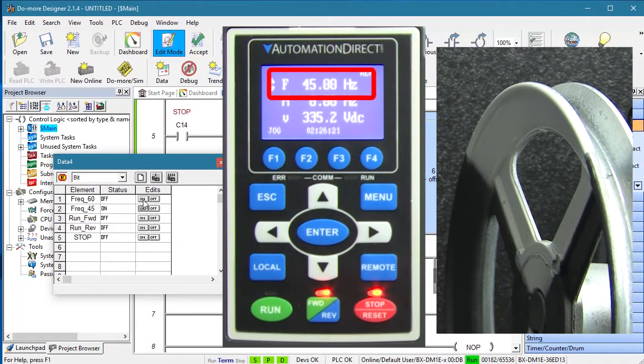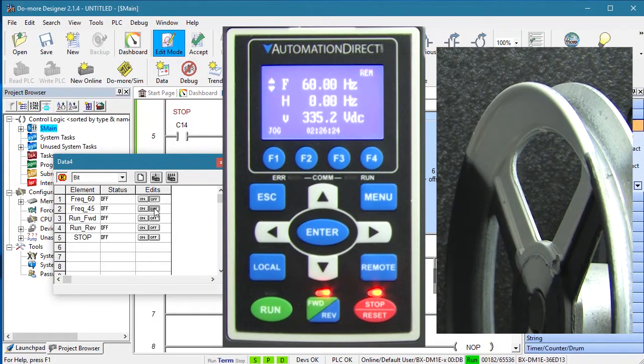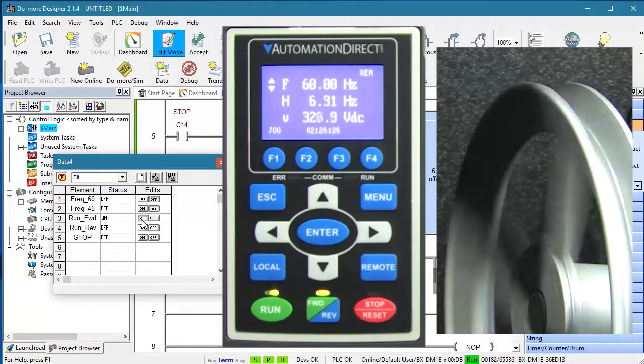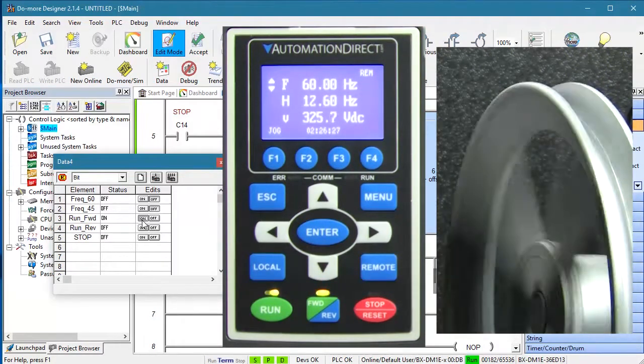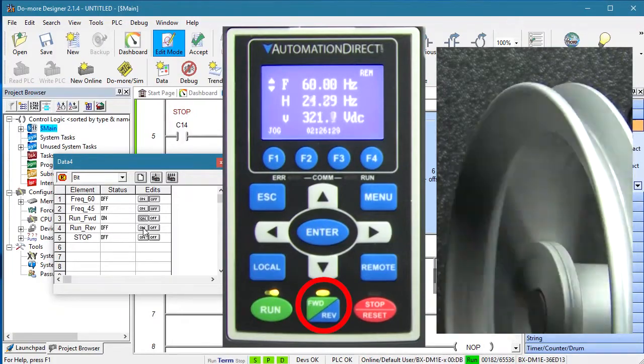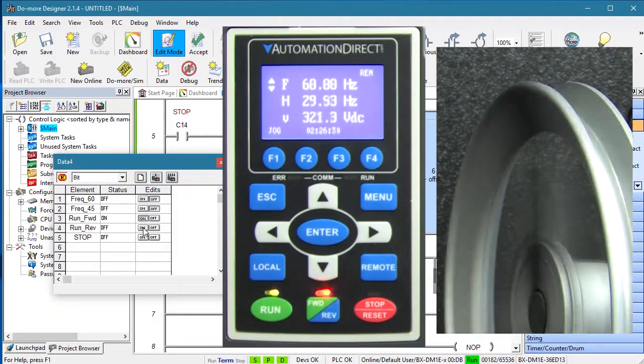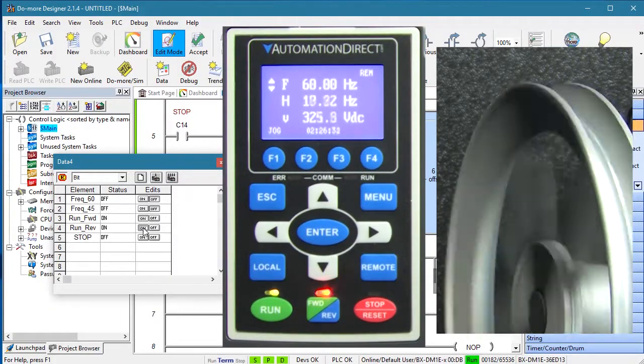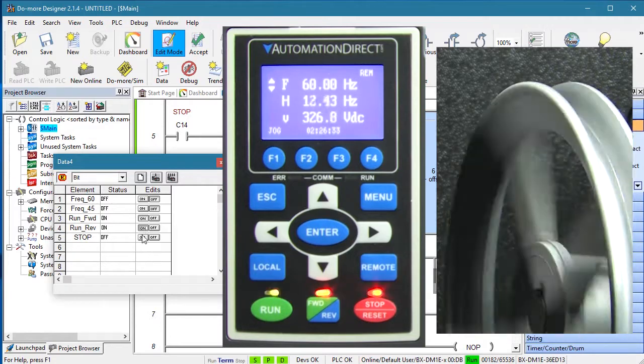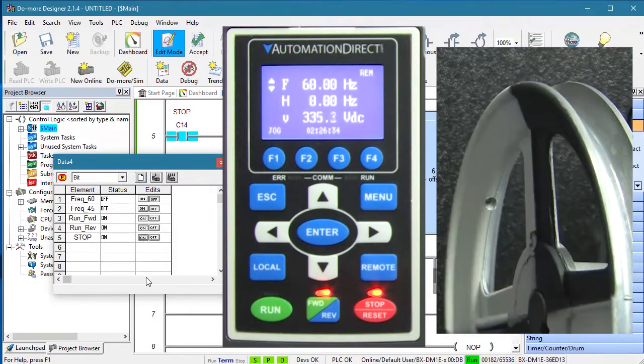If we activate the 60 Hz instruction, the drive reacts accordingly. If we toggle the run instruction, the motor starts turning and we see that it is in the forward direction. Toggle the reverse contact and the motor changes direction. And toggle the stop contact and the motor ramps to a stop. Exactly what we expected.